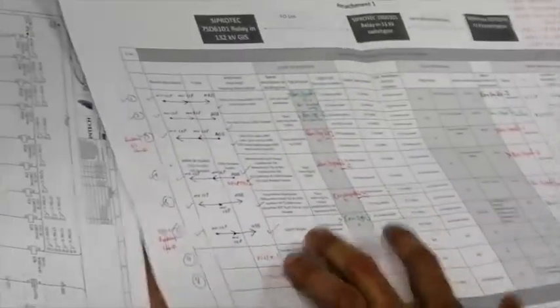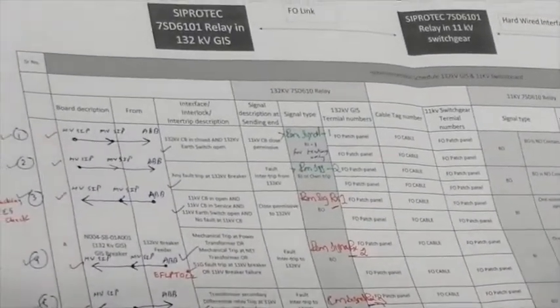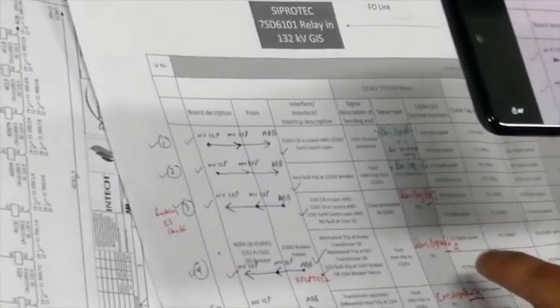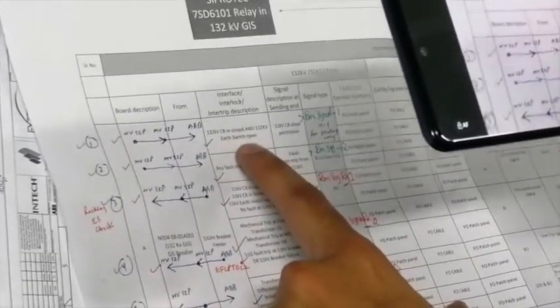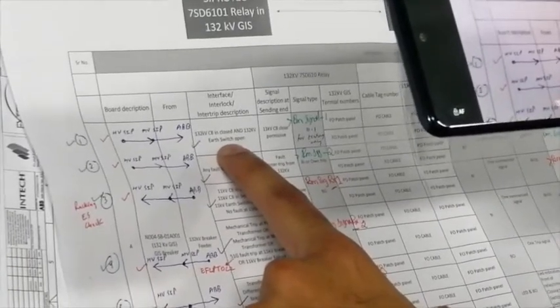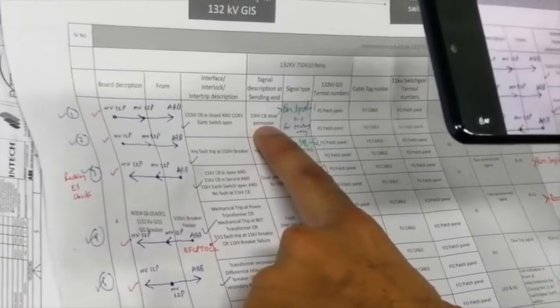Let's start the first signal. This is an overview of the signal list, which will be part of the signal test report. The first signal is the 132kV CB open or closed status sent to the 11kV SIPROTEC relay — meaning if the 132kV circuit breaker is closed, we have permission to close the 11kV circuit breaker.